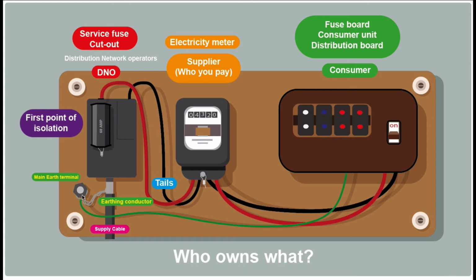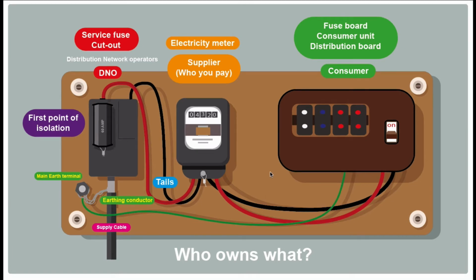The DNO is also responsible. If they provide an earth, they have to maintain that, but they don't have to supply an earth. You think of a TT type system, there's no earth supplied there, but if they do provide an earth, it's their duty to maintain it.